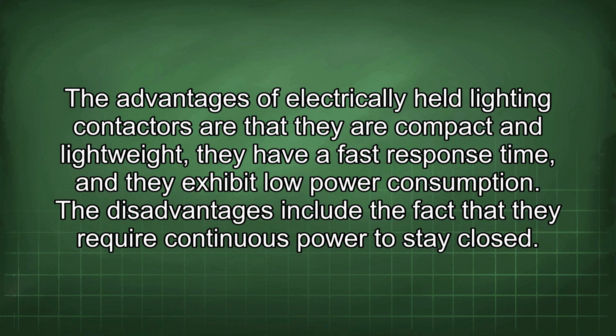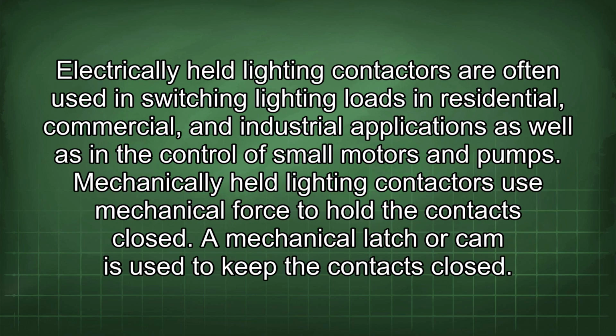The advantages of electrically held lighting contactors are that they are compact and lightweight, they have a fast response time, and they exhibit low power consumption. The disadvantages include the fact that they require continuous power to stay closed. Electrically held lighting contactors are often used in switching lighting loads in residential, commercial, and industrial applications, as well as in the control of small motors and pumps.